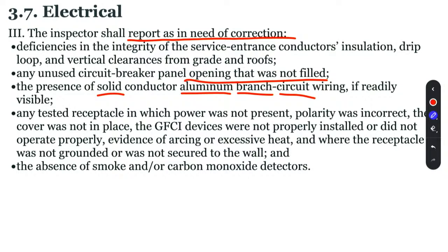All right. Any test of a receptacle in which power was not present, polarity was incorrect, the cover was not in place, the GFCI devices were not properly installed or did not operate properly, evidence of arcing or excessive heat, and where the receptacle was not grounded or was not secured to the wall. And then also the absence of smoke and carbon monoxide detectors.